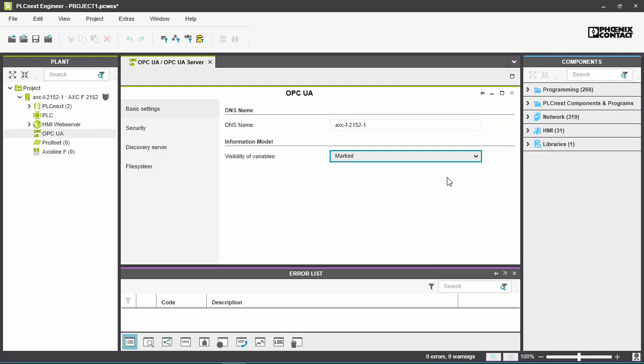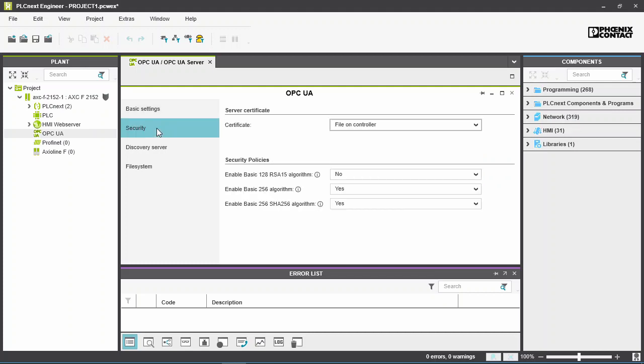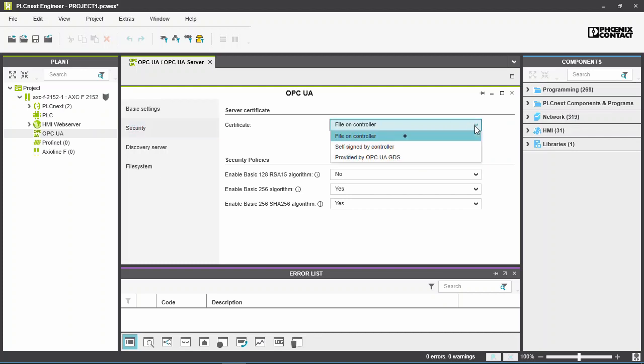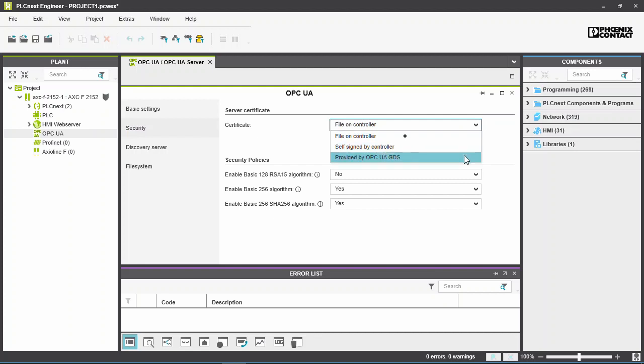Check the security settings. The OPC UA server requires a security certificate. This can be provided by the user, or generated automatically by the PLC, or obtained from a global discovery server.